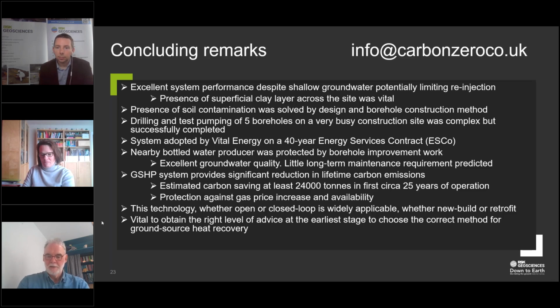There's a fairly straightforward formula for computing what flow rate you need to meet a given heating or cooling load. Like we said, 60 litres a second at the Berkeley Homes example provides about 1.5 megawatts of peak heating. And in some cases, the processed water will be at a higher temperature than background anyway, so you've got an advantage there of extra free heat available that you can use for something else, making the system even more efficient.